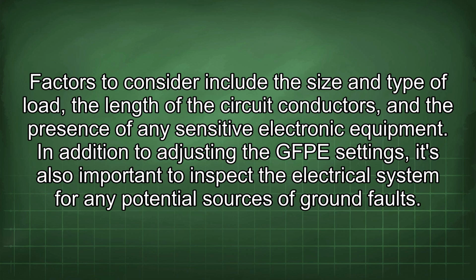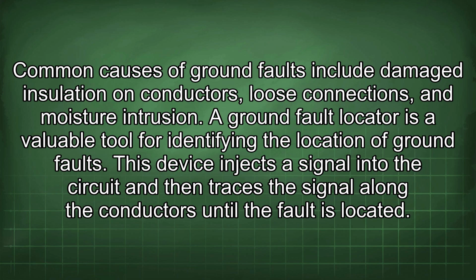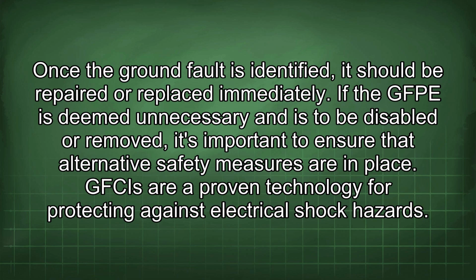In addition to adjusting the GFPE settings, it's also important to inspect the electrical system for any potential sources of ground faults. Common causes of ground faults include damaged insulation on conductors, loose connections, and moisture intrusion. A ground fault locator is a valuable tool for identifying the location of ground faults. This device injects a signal into the circuit and then traces the signal along the conductors until the fault is located. Once the ground fault is identified, it should be repaired or replaced immediately.